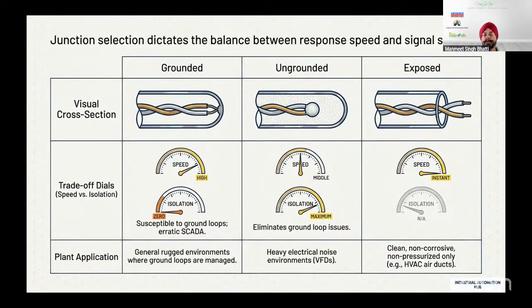So whenever the heat is coming into the body, the response speed is very fine. Okay, it's very, very high. As soon as the temperature comes, it touches the sheath, and automatically you will find a temperature coming. So the speed of response is very high, but the problem is also there.